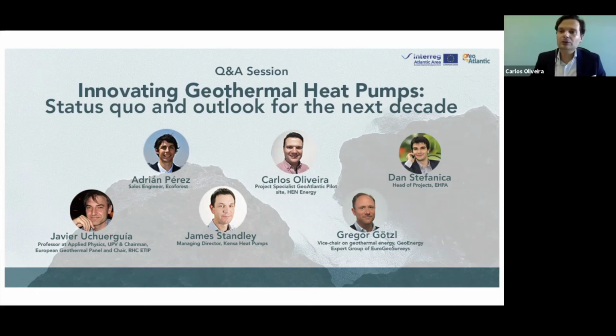To be honest, the first retrofitting I did with a heat pump was this one, and I've done maybe 100 to 150 retrofittings in buildings here in Portugal. Normally I change to boilers that work with wood or pellets rather than heat pumps, because we face several technical issues when changing a boiler to a chiller or heat pump.